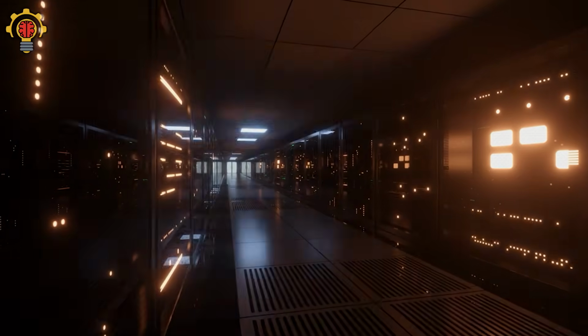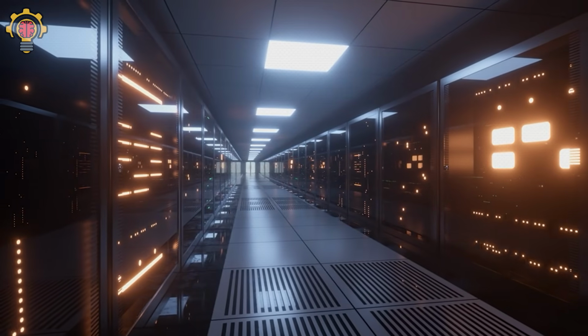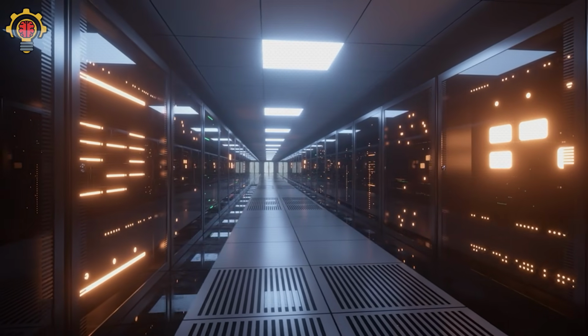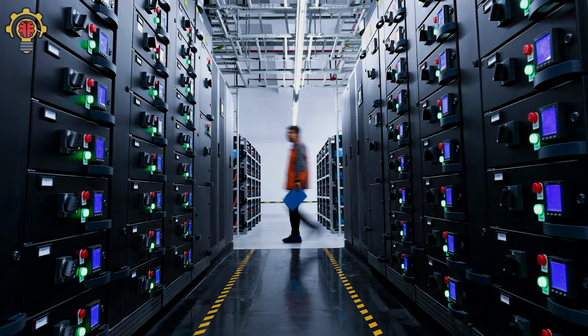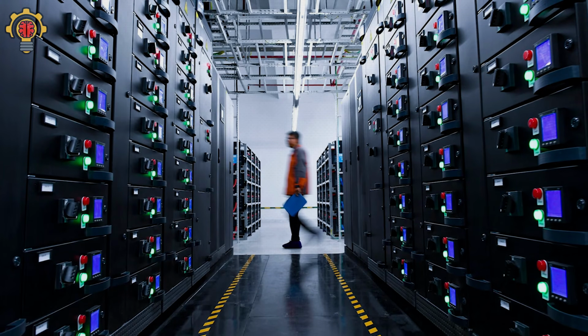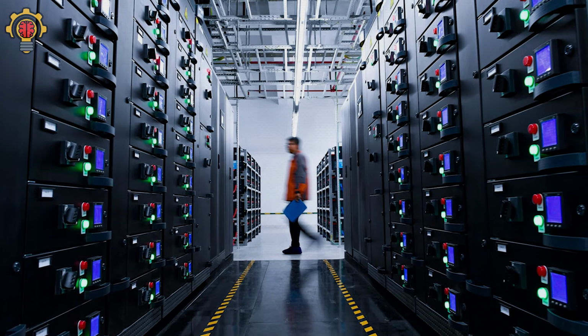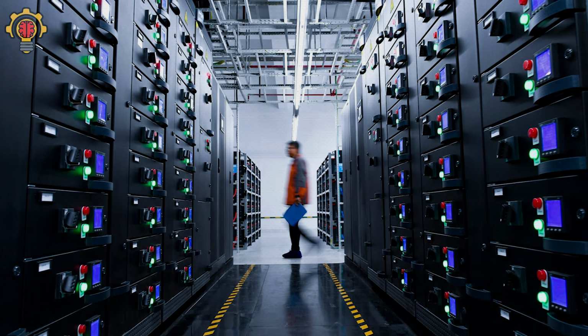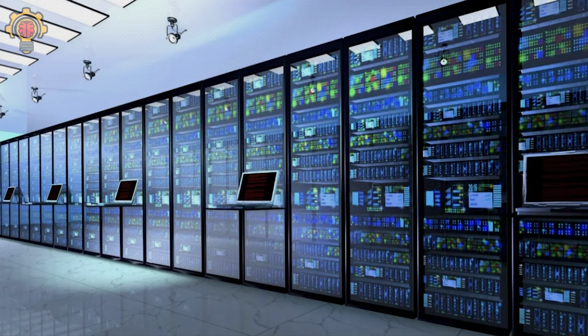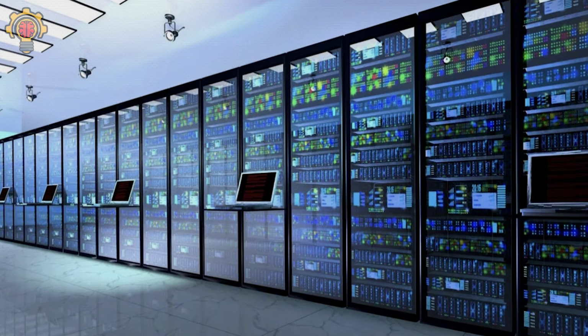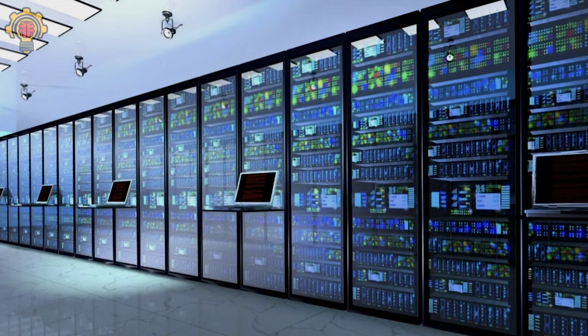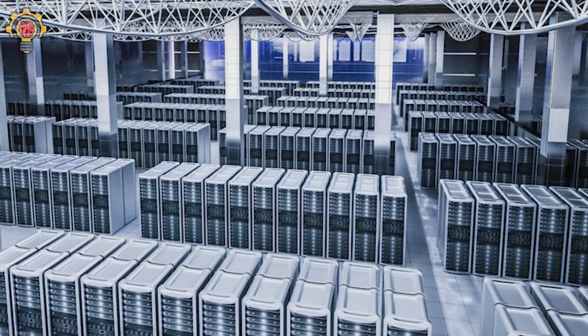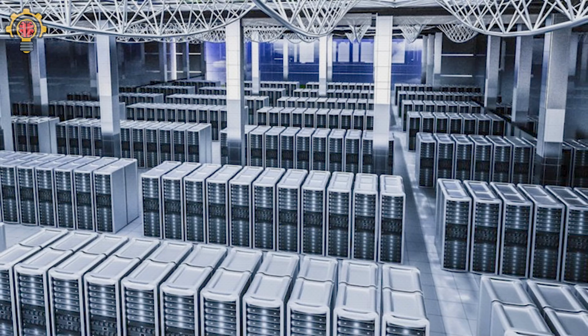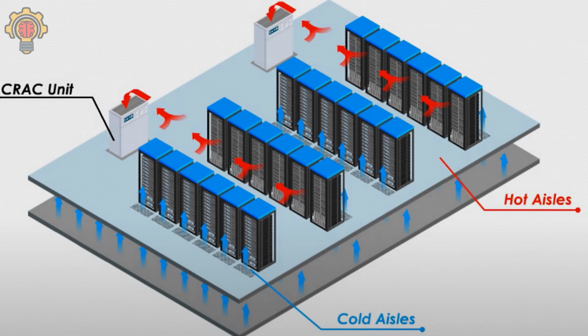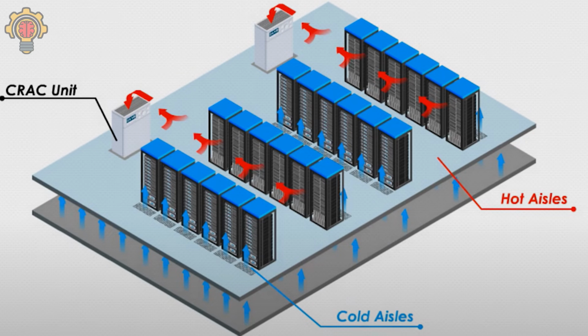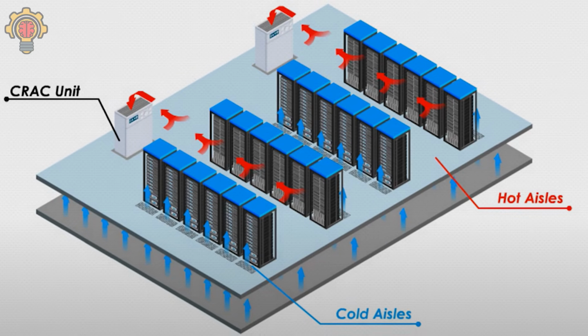But even advanced airflow systems have limits. Air simply cannot remove enough heat fast enough for some modern workloads. And that is exactly why liquid cooling is becoming one of the biggest trends in the industry. Liquid transfers heat far more efficiently than air. Some liquid cooling systems can remove several times more heat than traditional airflow systems. One method uses rear-door heat exchangers mounted behind server racks. As hot air exits the servers, liquid-cooled coils absorb the heat almost instantly.